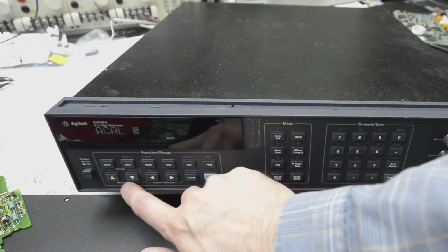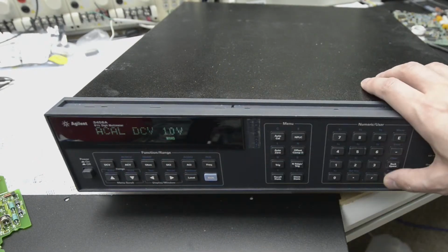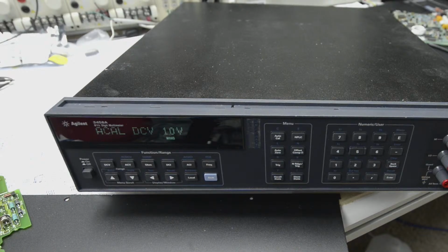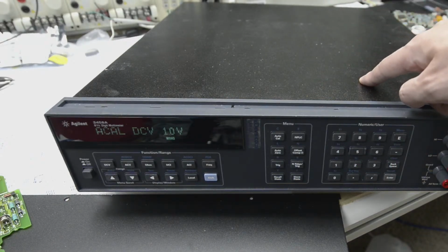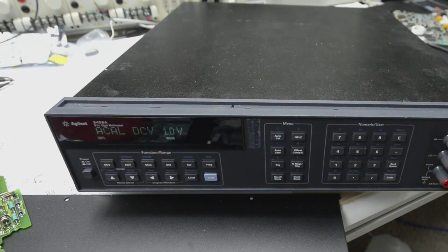Right now it's because we don't have the ACAL done. The ACAL values for this board are incorrect because we ran the ACAL with another board. This is quite an interesting observation, because it means if you are unable to pass ACAL all, you will have incorrect EEPROM contents for all the corrections, the flatness, and the offsets. That would cause those bogus values. So you need to be able to pass ACAL to validate that the A2 board is working, and if you cannot, then you have a hardware fault.